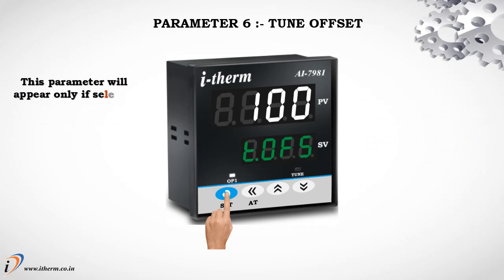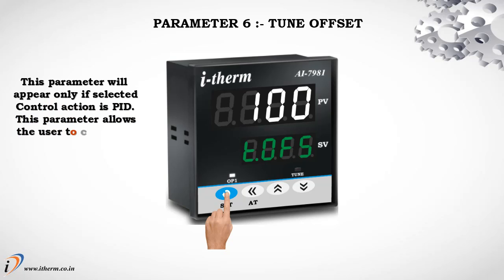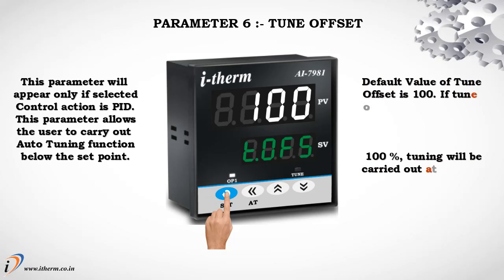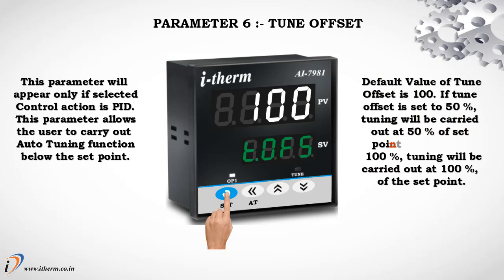Parameter 6: Tune Offset. This parameter will appear only if selected control action is PID. This parameter allows the user to carry out auto-tuning function below the set point. Default value of tune offset is 100. If tune offset is set to 50%, tuning will be carried out at 50% of set point; if set to 100%, tuning will be carried out at 100% of set point.